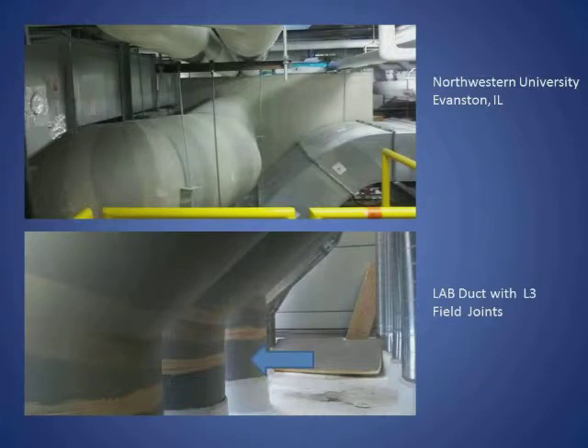Here's an example, Northwestern University, Evanston, Illinois. There's a 5-story building of new laboratory, and the fiberglass duct serves fume hoods on all 5 floors. And we're looking at some photos of the mezzanine area where it all comes together. The lower picture, you get a good look at an L3 joint, which is our low VOC joint, which we'll explain in a minute.